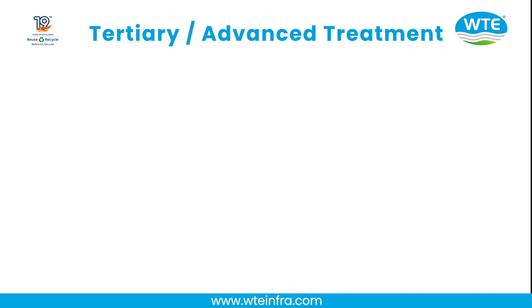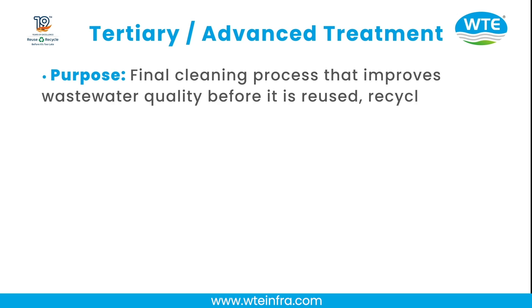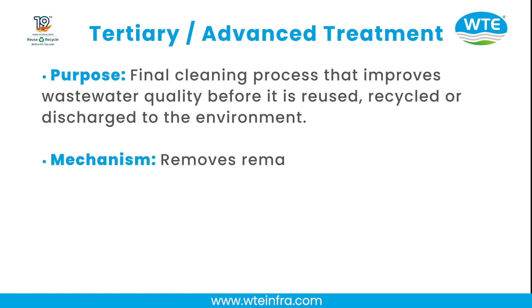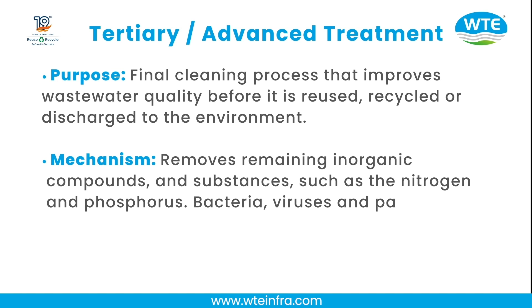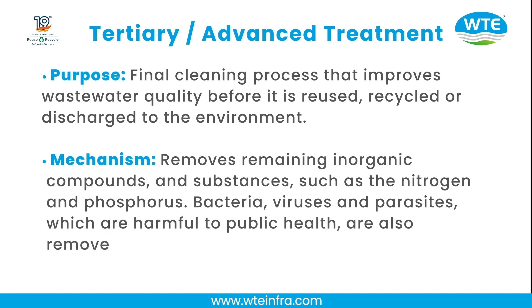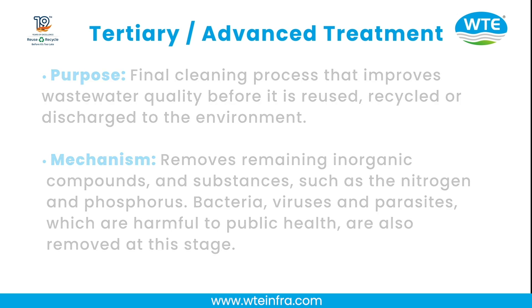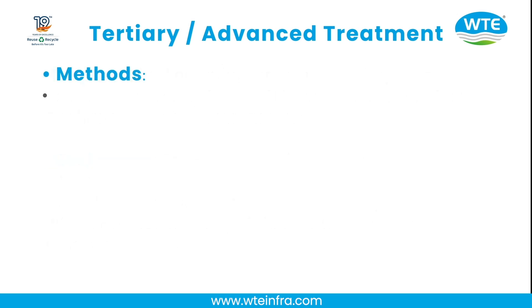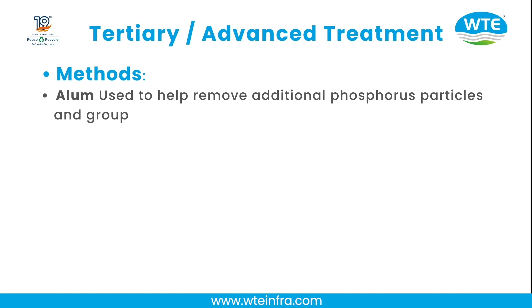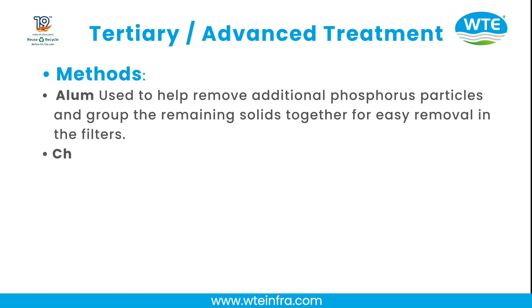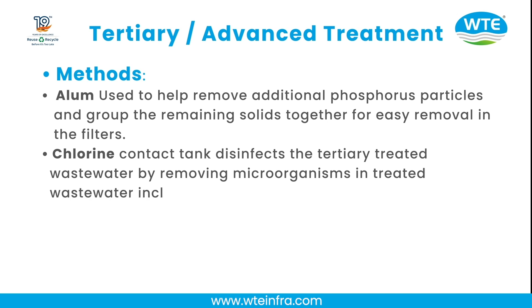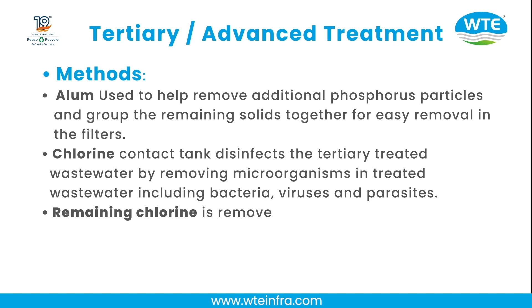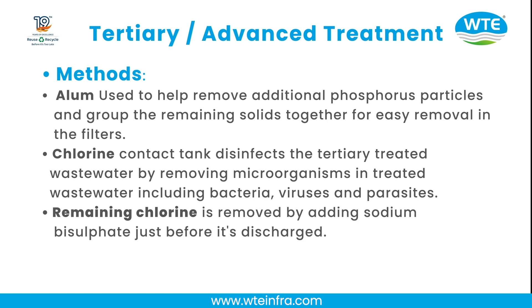Tertiary or Advanced Treatment: Purpose is the final cleaning process that improves wastewater quality before it is reused, recycled, or discharged to the environment. It removes remaining inorganic compounds and substances such as nitrogen and phosphorus. Bacteria, viruses, and parasites harmful to public health are also removed at this stage. Methods include using alum to remove additional phosphorus and group remaining solids for easy filtration, and a chlorine contact tank to disinfect the tertiary-treated wastewater. Remaining chlorine is removed by adding sodium bisulfate before discharge.